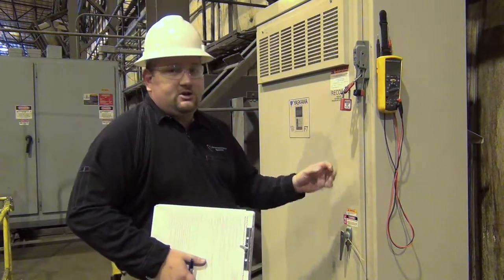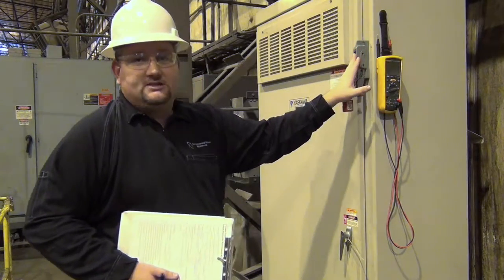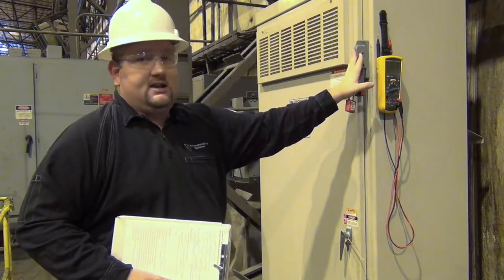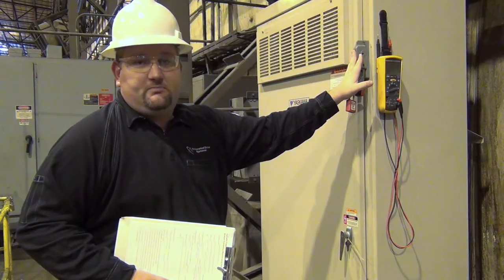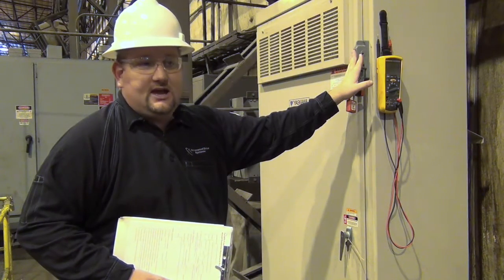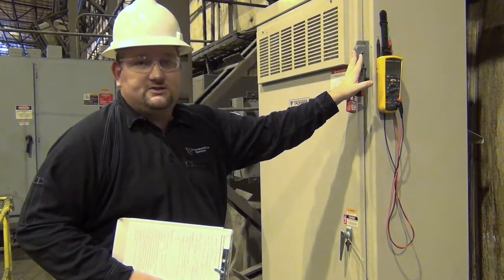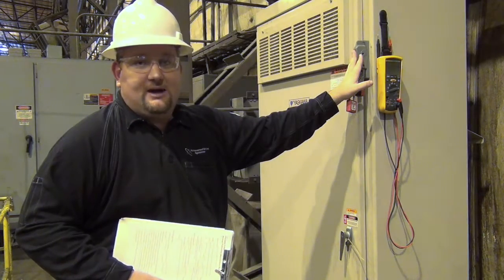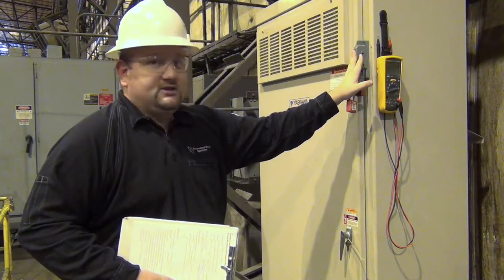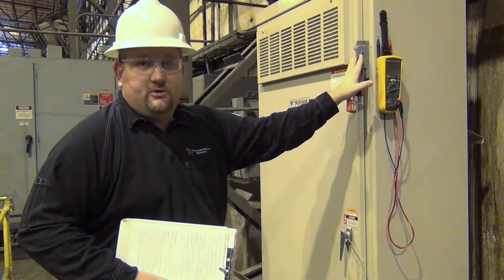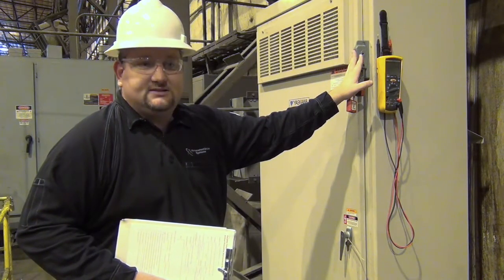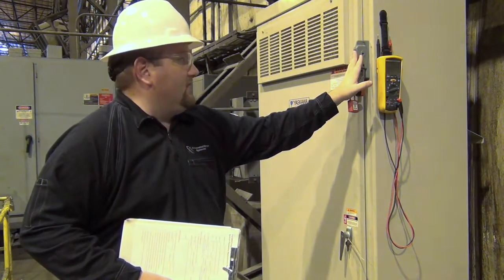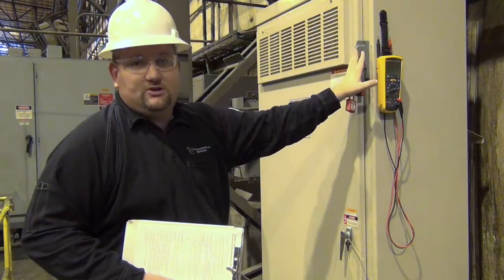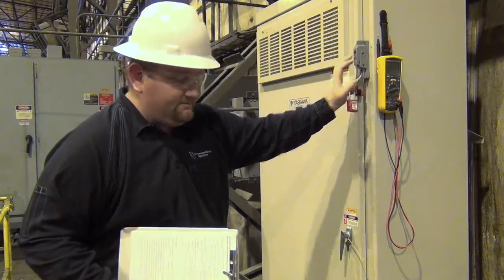So the very first thing we're going to do, obviously, is make sure that the equipment is locked out. Like I said, follow any of your company's PPE requirements as far as doing that. And then obviously the very first thing we'll do is verify that the power is dead. We've actually already done that before starting film, but we'll go through that process again. Like I said, if your facility requires PPE for this check, make sure you follow your facility's guidelines.